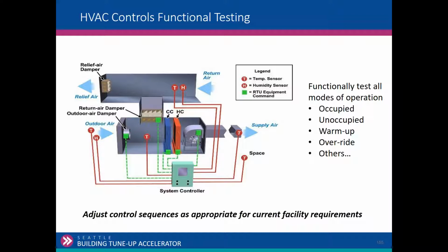In the unoccupied mode, what should be the status of the system? What's the fan status? Off. Right, we can see that. We can physically do that. What's the outside air damper position? Closed. Right? Otherwise, it's just a hole in the building. Might as well leave the window open. And then we can also verify through warm up. And for those that have done commissioning, you know how you've kind of put these BAS systems through their paces, right? So you make changes in the set points, you initiate these control actions, and we can observe operations and override systems and make sure that we're doing everything.